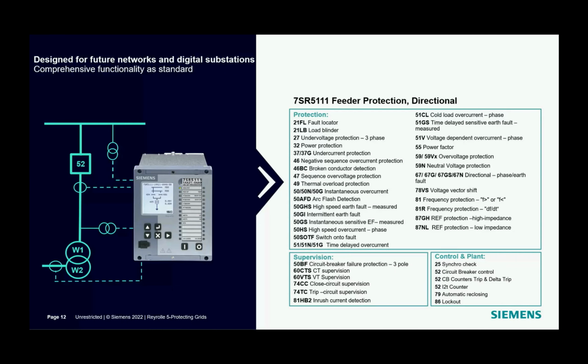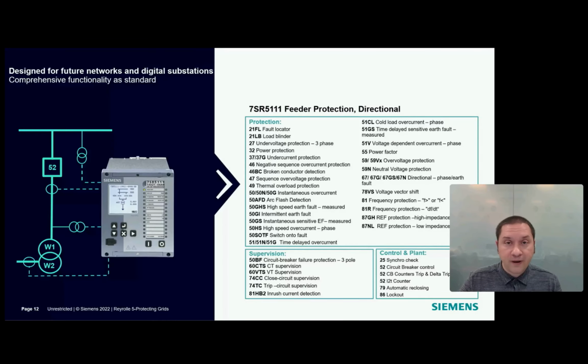7SR5121, and you may have already realized that there's a power transformer in the concept scheme. With the 5th CT, these are typically used in transformer circuits. With a 5th current transformer input, you can use a single device which provides measured standby earth fault protection of transformer earthing resistors. In addition to high impedance earth fault protection, overcurrent, and calculated earth fault protection, you can also apply a measured standby earth fault protection to the transformer earthing resistors at the same time with a single device.